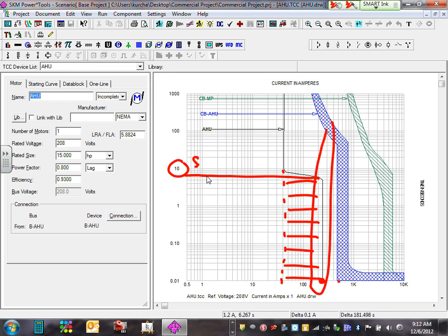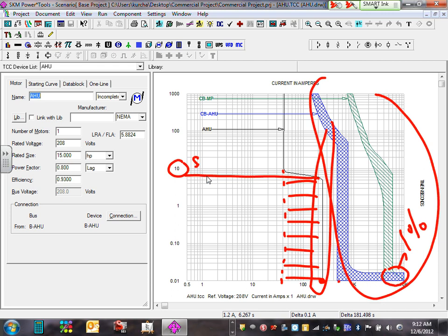The second thing is, can you guys see these two curves are not touching each other? The only time they miscoordinate is right in here, which is 1% of the time. Can you guys see that? So we're only miscoordinating 1% of the time. They're as fully coordinated as you can get. So that's basically what coordinating these two together means.